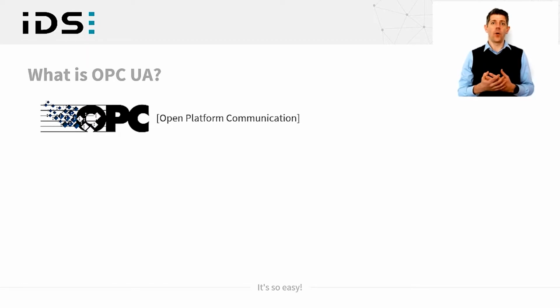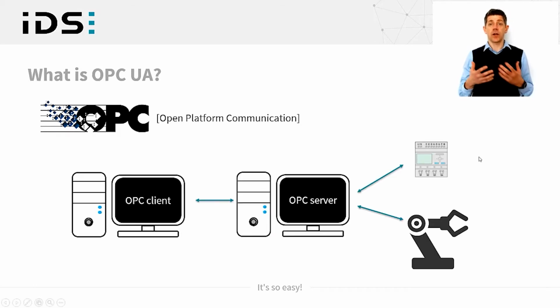OPC stands for Open Platform Communication, or at least has evolved to this definition. It's been around since the mid-1990s, with the original or classic OPC standard allowing some level of manufacturer independence for the data exchange through a server-client relationship. But this still required hardware manufacturers to provide specific drivers and was based only on the Windows operating system.